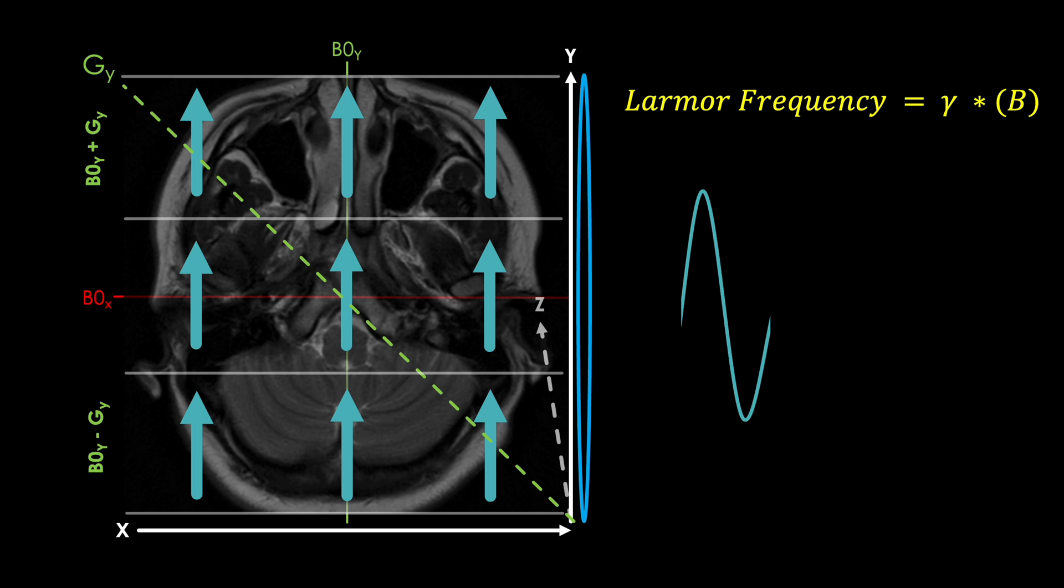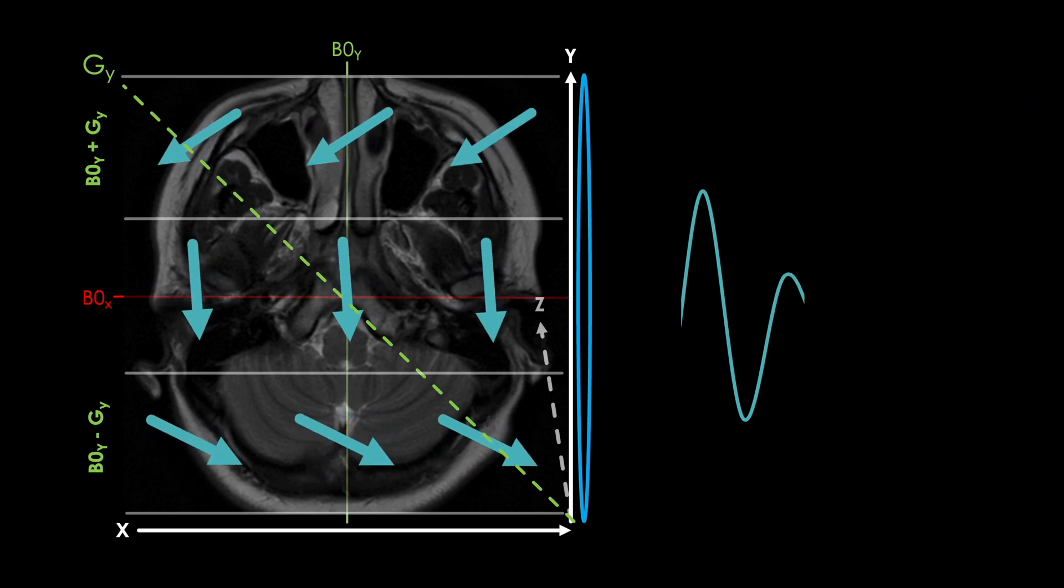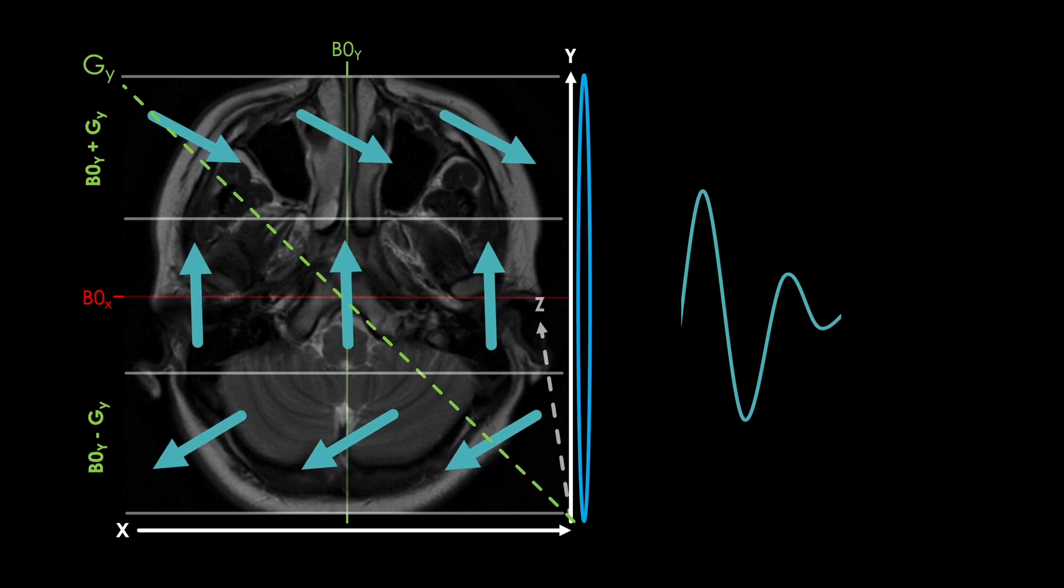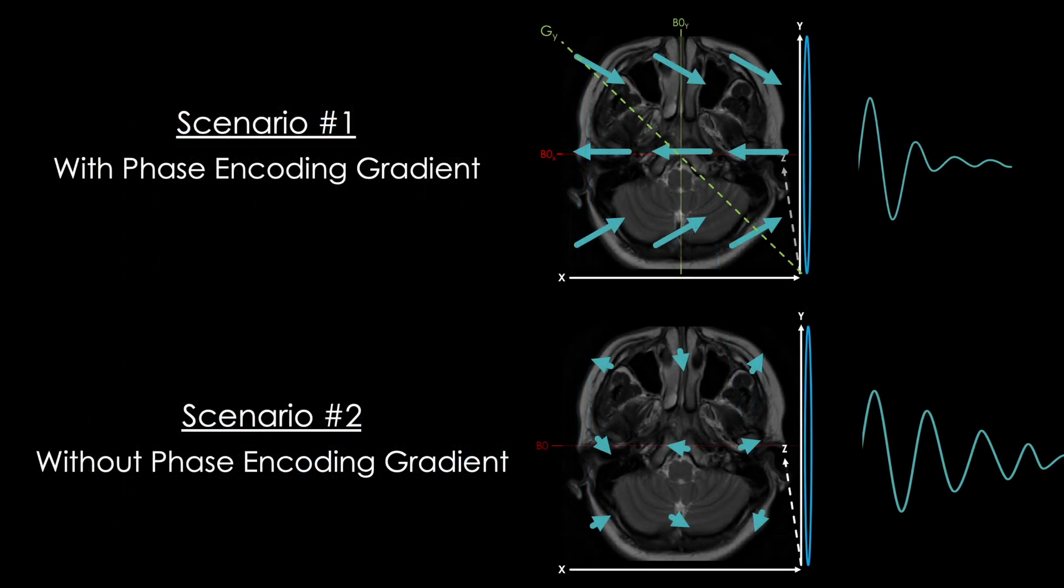So as long as this gradient field is applied, the protons in the top row will spin faster than the middle row, and the middle row will spin faster than the bottom row, and this will directly impact our signal. You can now appreciate that with the phase encoding gradient, we are forcing a dephasing to happen separate from the natural T2 decay dominating the second scenario. And this dephasing occurs the moment we turn this gradient on. It also doesn't affect every single proton like in our second scenario, but is spatially confined to rows within the image, thus somewhat preserving the net magnetizations within the voxels themselves.